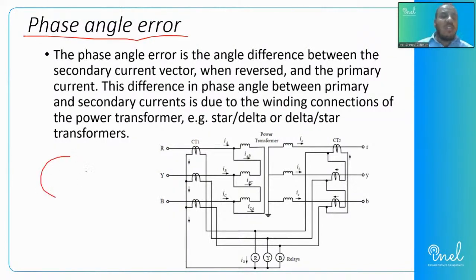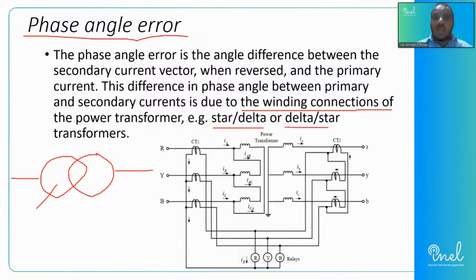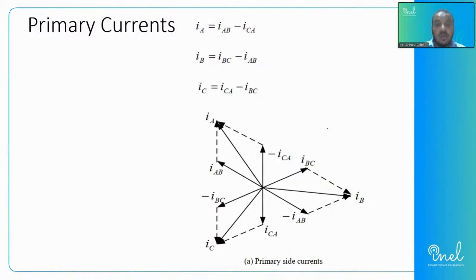And usually we have a three-phase primary side and a three-phase secondary side, especially when applying our protection on a three-phase transformer. Such a three-phase connection is either star delta, delta delta, or delta star. So based on the winding connection between both sides, there may be some phase angle shift or phase angle difference between both sides. So we should also take care that the phase angle error between both sides would affect the operation of the differential relay. The differential relay would be affected by the connection of the power transformer, whether star delta, delta star, and so on. At the end we have a three-phase system.